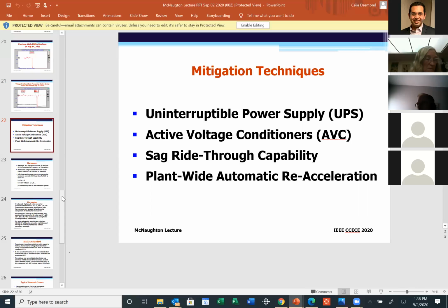when you lose the power completely or you have a severe voltage loss, because the UPS concept has batteries. Just like your car, when you want to start it, you have to have a battery. Here, the UPS has internal batteries in it. During these disturbances, the device is switched to the batteries that support the computer loads. The second option, active voltage conditioner, does not use batteries. When you don't use batteries for the protection, then the protection duration is very, very limited. With a UPS, you can protect your equipment typically for 10, 15, even 20 minutes, depending on the design. With an active voltage conditioner, off the top of my head, I think less than a second, because it doesn't have batteries.